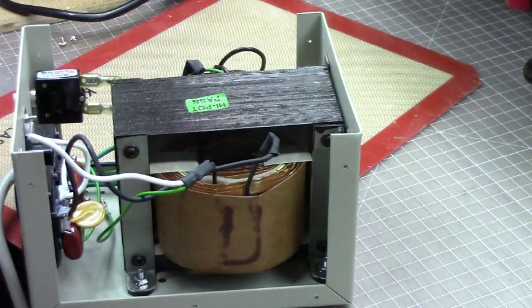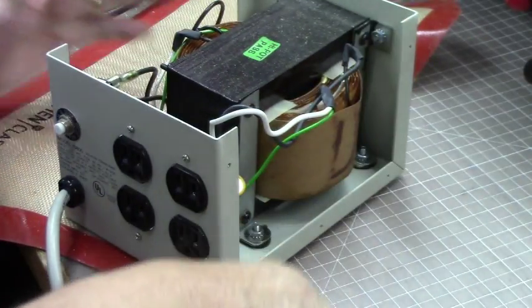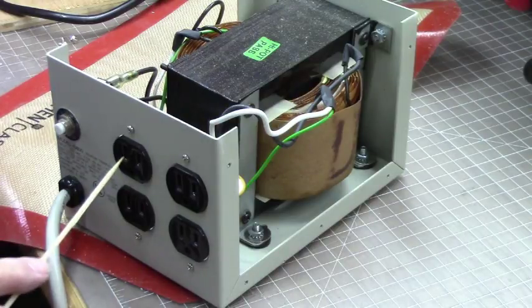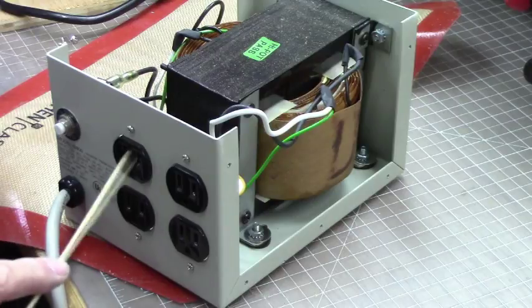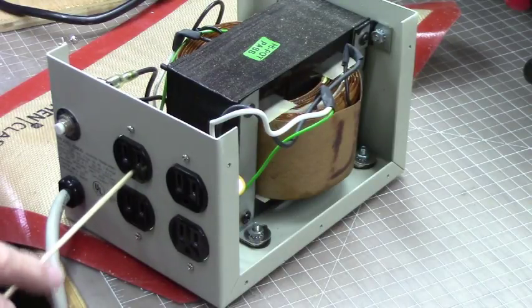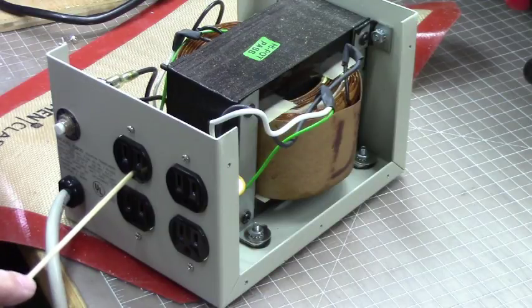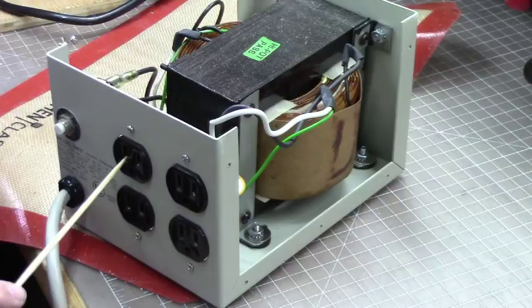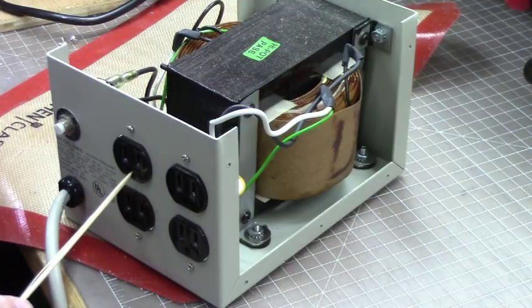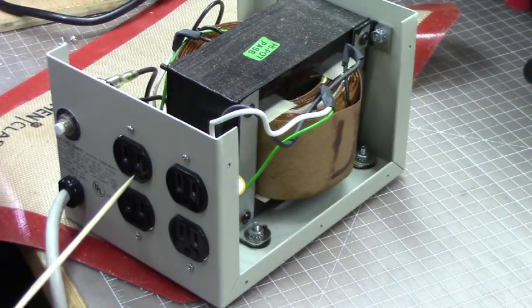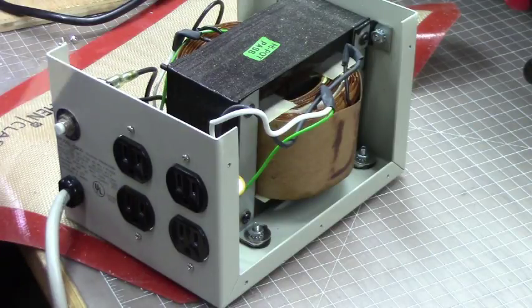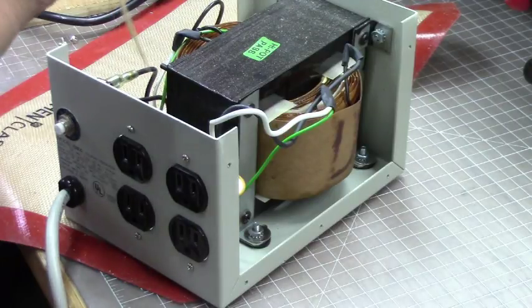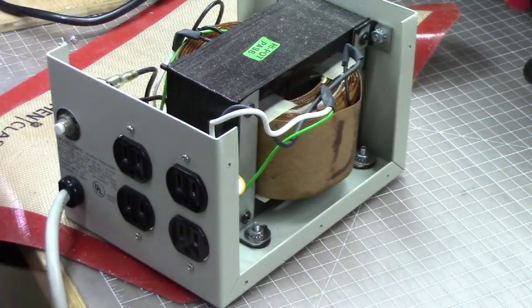Excuse me, the problem with that is your hot and your neutral are definitely isolated. However, you still have a ground connected here. Now, what happens is, if you were to short one or the other to ground, you would still get a shock, perhaps lethal. That's why this is not a good thing. Easily remedied though - all we have to do is take off the grounds and we'll be good to go.